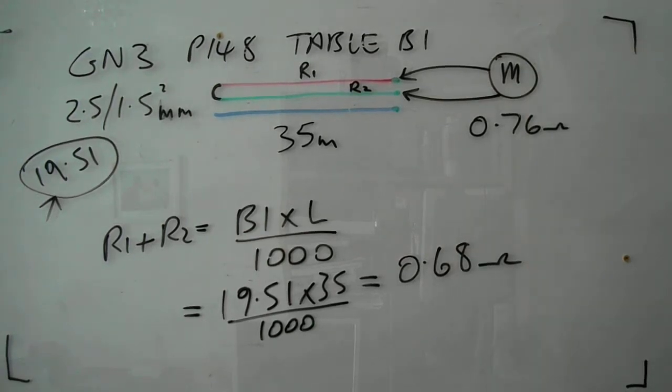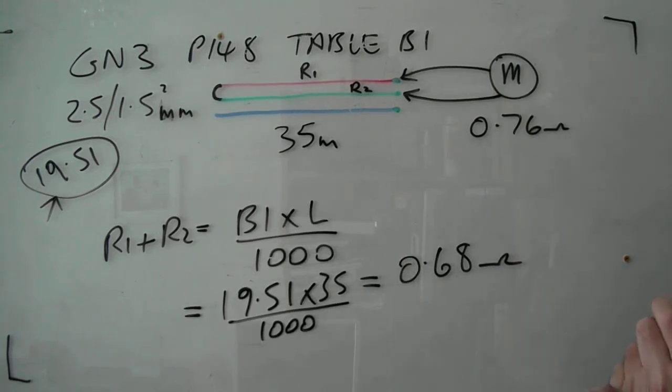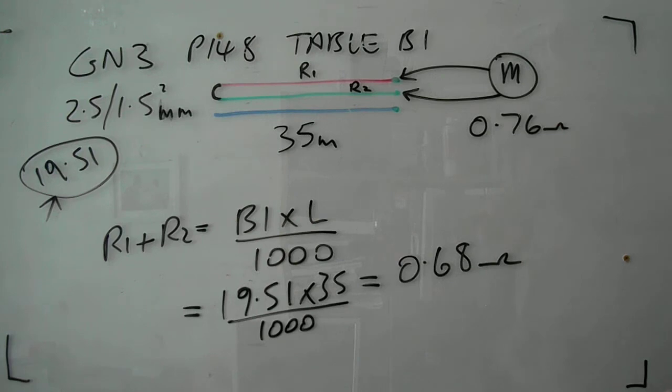So you can see there, this is the sort of figure you're expecting and this is the figure you're measuring. So you've got to make a decision as to whether that's acceptable or not. I would say it's probably a little bit suspect. I would check all the connections in that line to make sure they were OK to see if you can get it down to a bit more of what you expect.